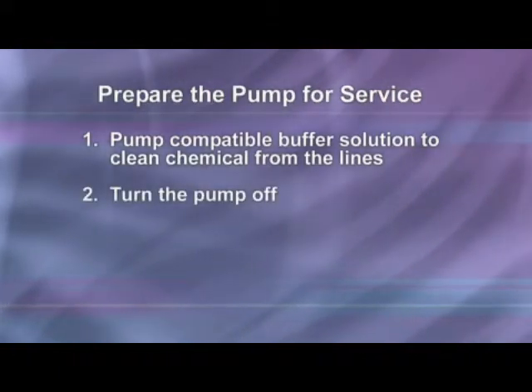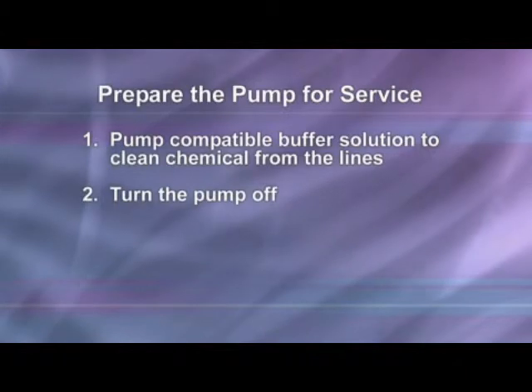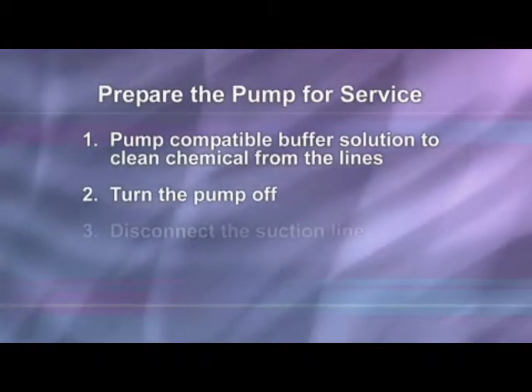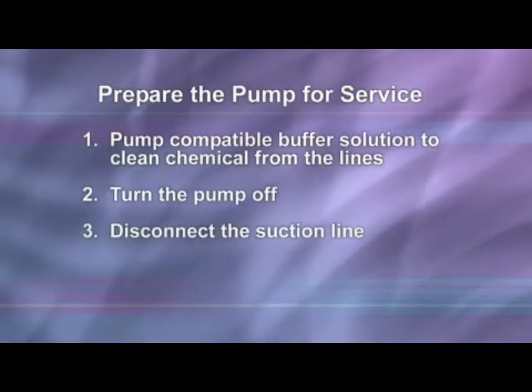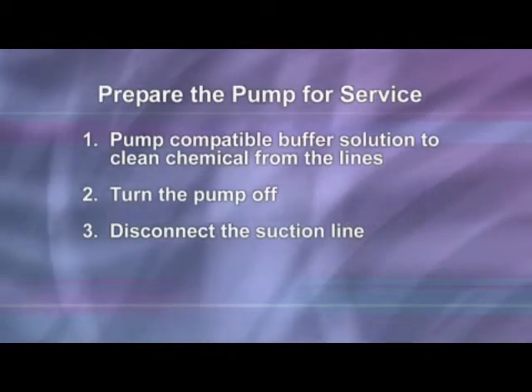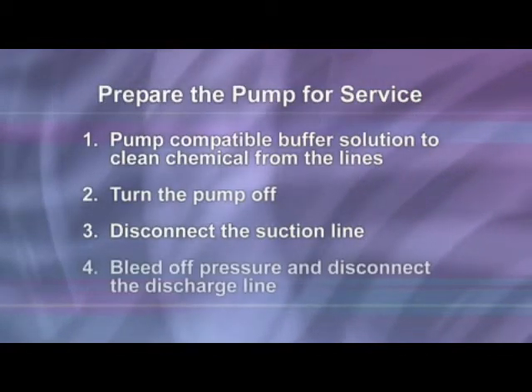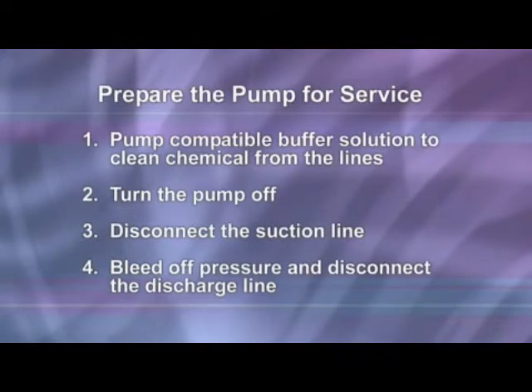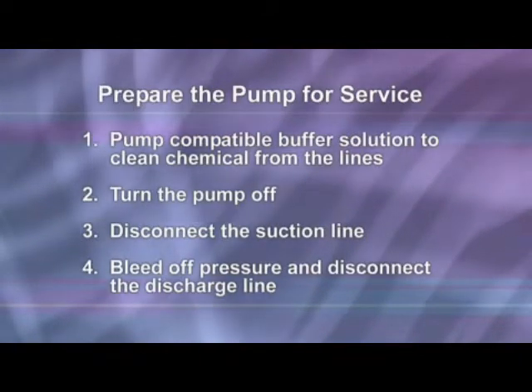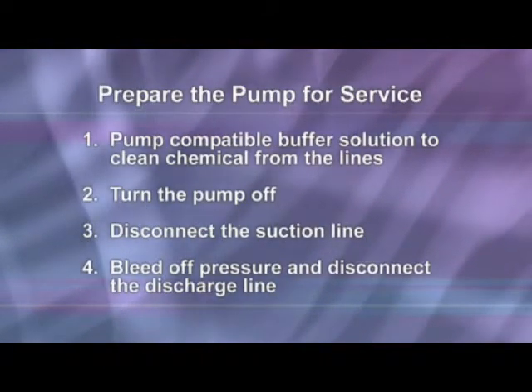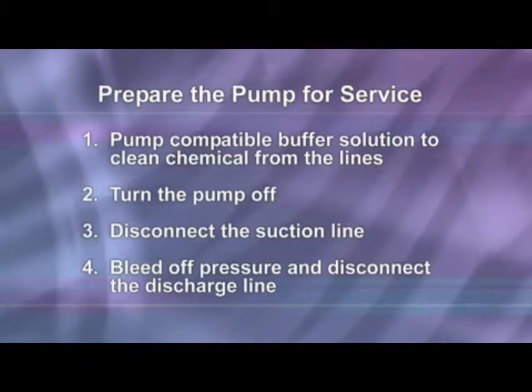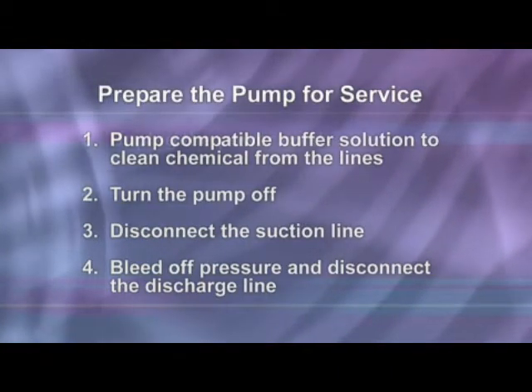Turn the motor on-off switch to the off position, which is down or to the rear of the pump. Disconnect the suction line from the pump tube suction fitting labeled in the pump head cover. Before disconnecting the discharge side, bleed off any pressure. Then, disconnect the discharge line from the pump tube discharge fitting, labeled out on the pump head cover.